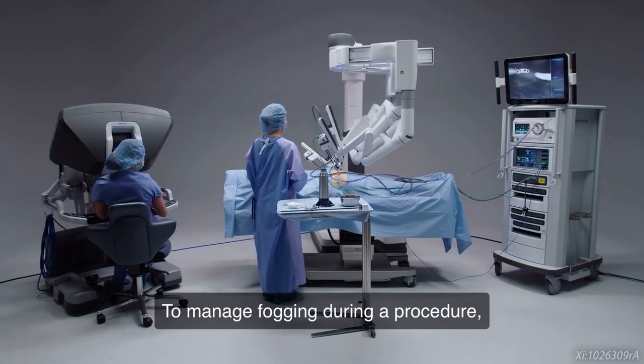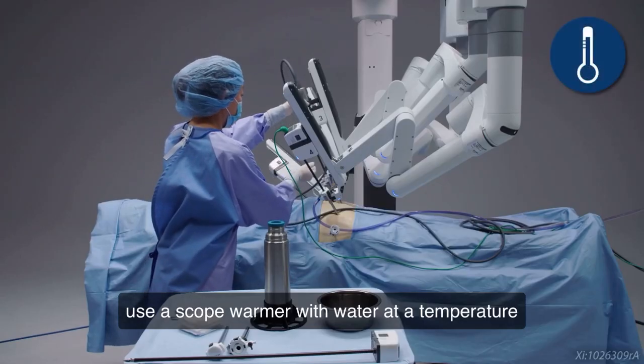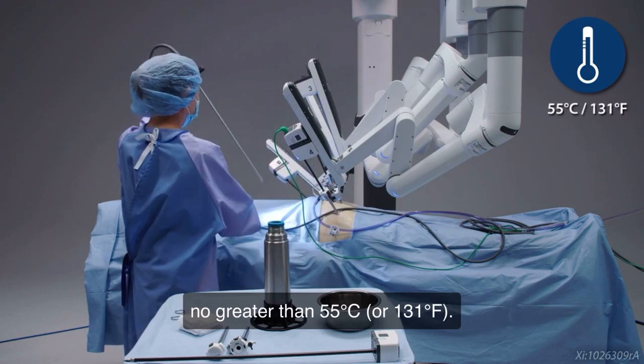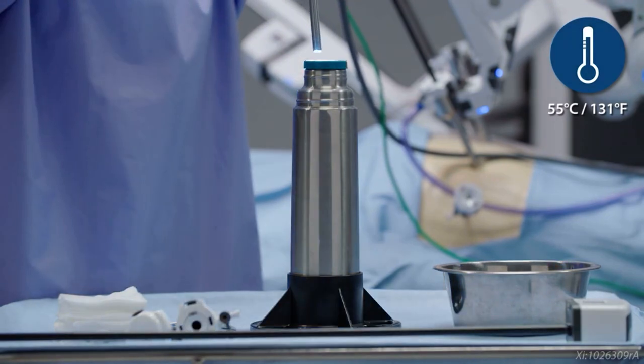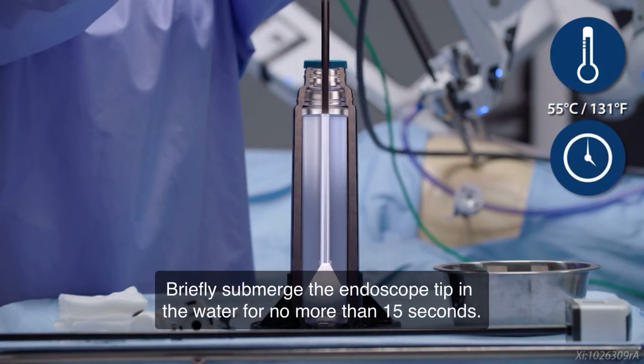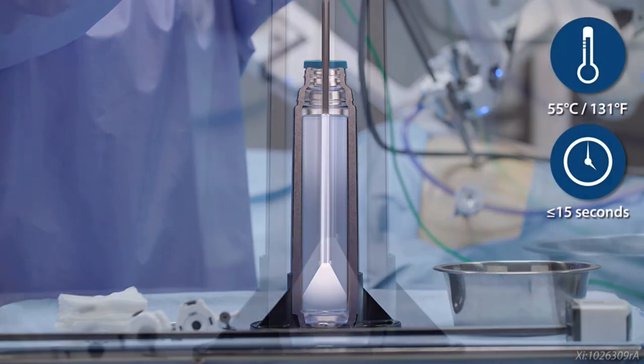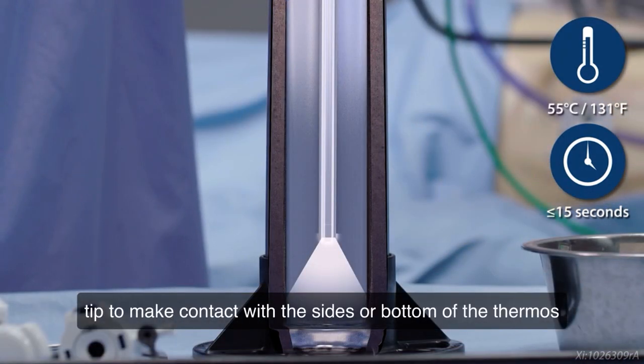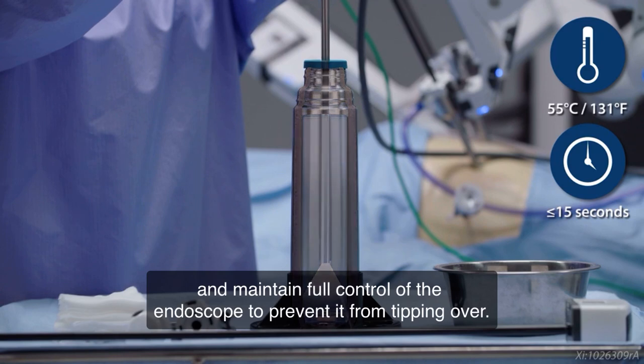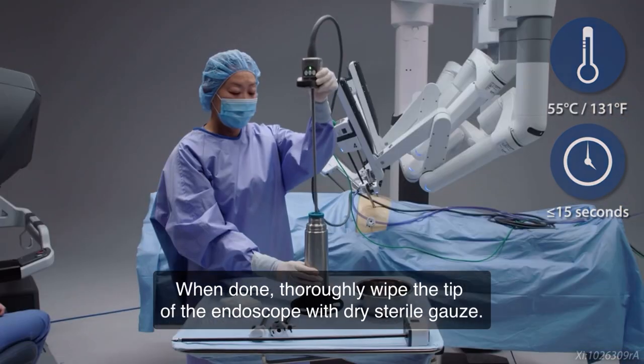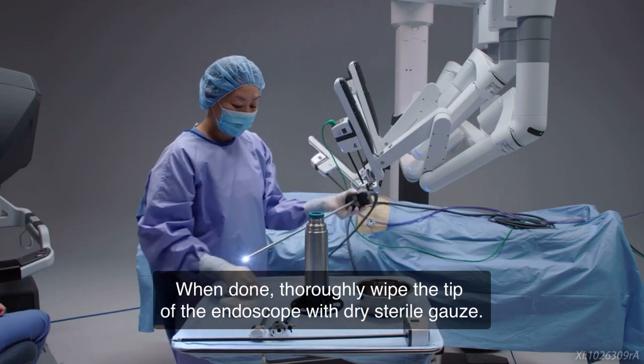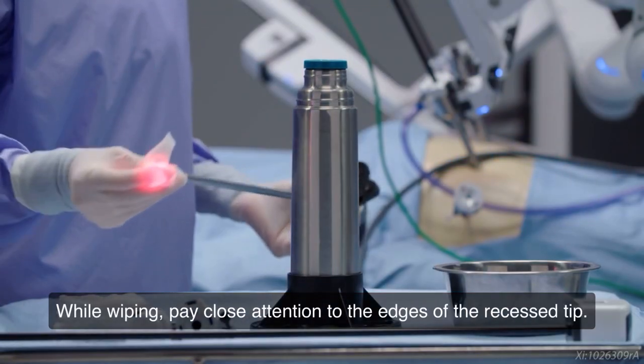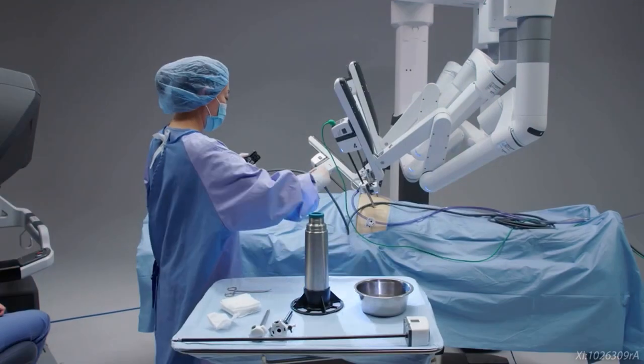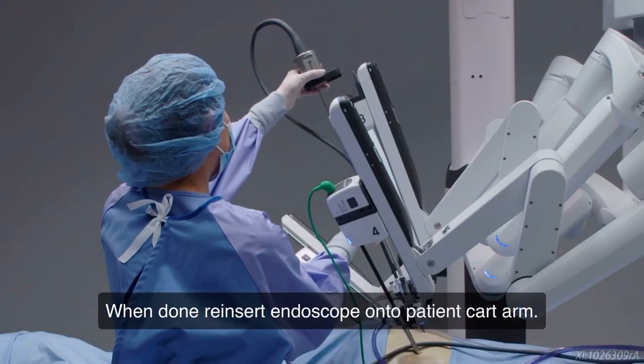To manage fogging during a procedure, use a scope warmer with water at a temperature no greater than 55 degrees Celsius or 131 degrees Fahrenheit. Briefly submerge the endoscope tip in the water for no more than 15 seconds. If using a thermos, do not allow the endoscope tip to make contact with the sides or bottom of the thermos, and maintain full control of the endoscope to prevent it from tipping over. When done, thoroughly wipe the tip of the endoscope with dry, sterile gauze. While wiping, pay close attention to the edges of the recessed tip. When done, reinsert the endoscope onto the patient cart arm.